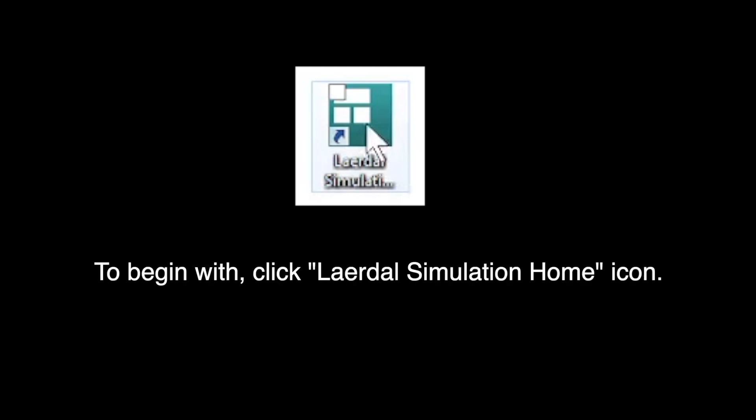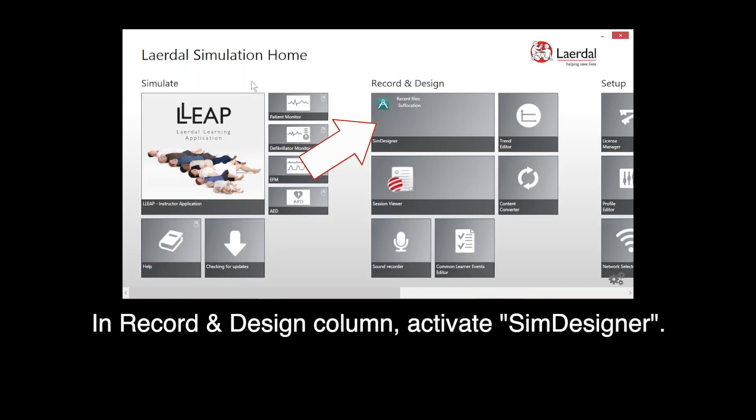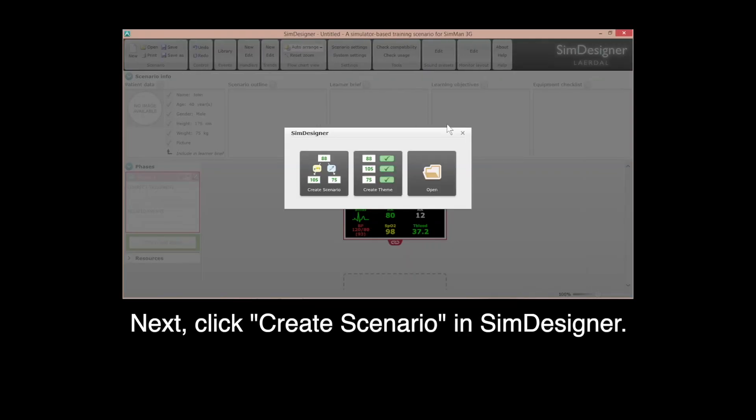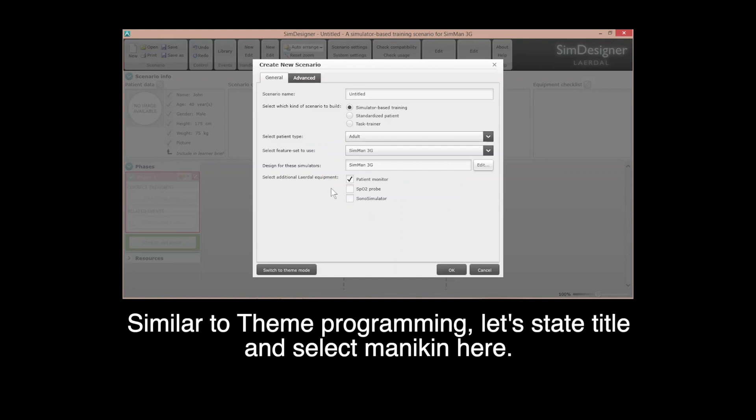To begin with, click the Laerdal Simulation Home icon. In Record and Design column, activate Sim Designer. Next, click Create Scenario in Sim Designer. Similar to Theme programming, let's state title and select MANIKIN here.